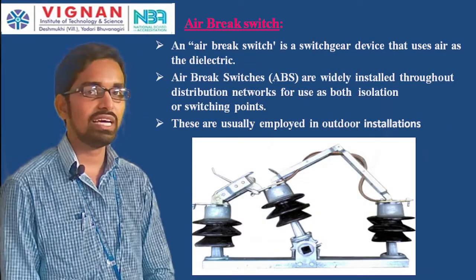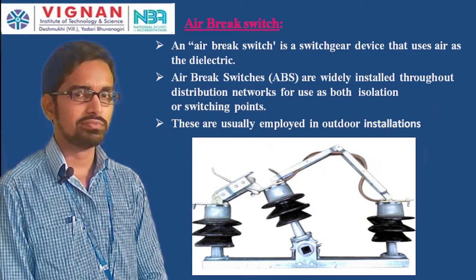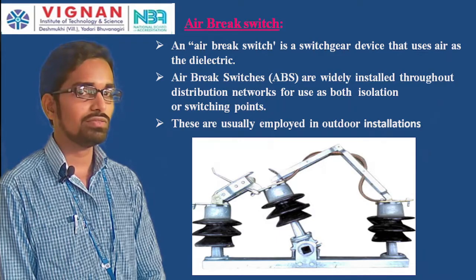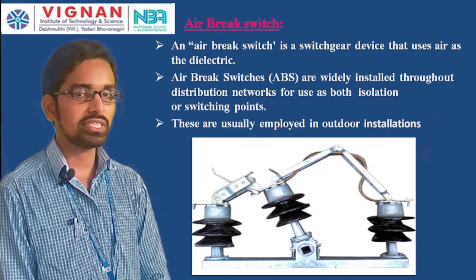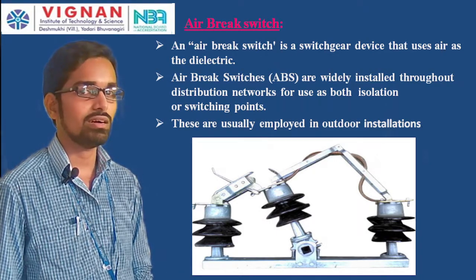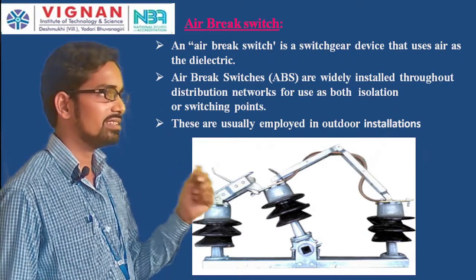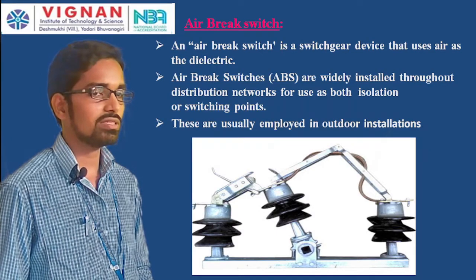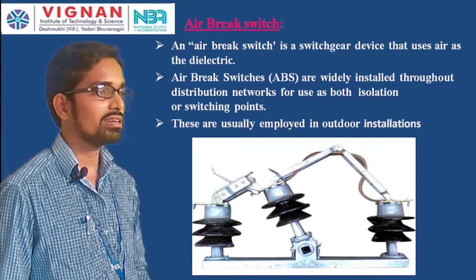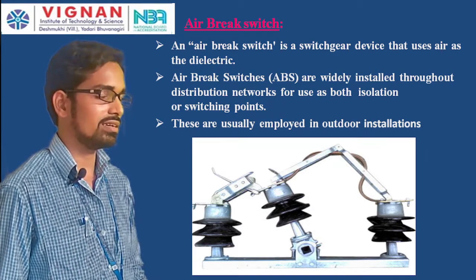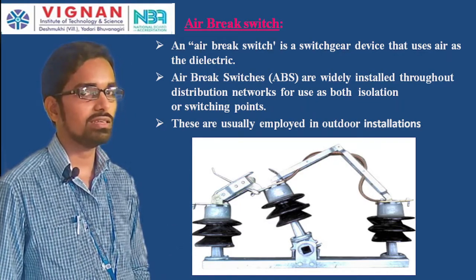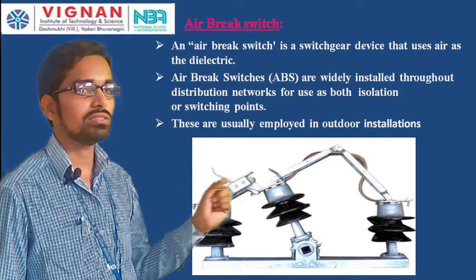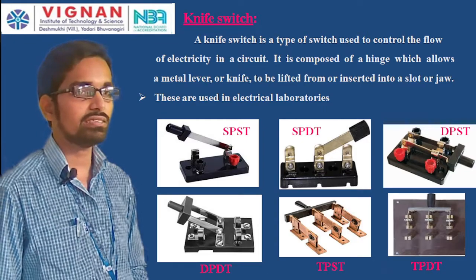An air break switch is a switchgear device that uses air as a dielectric medium. Air brake switches are widely installed throughout distribution networks for use as both isolation and switching points, commonly at distribution transformers — called gang switches — to switch the transformer on or off. They are used in outdoor installations only.